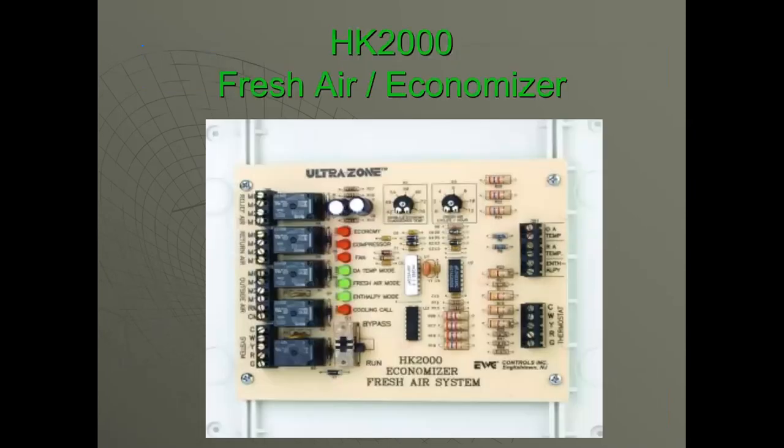As far as our product offering, I'm not going through the panels. I'm just throwing this out here. We do have a fresh air economizer panel. Anybody that's been around the Fort Worth, Dallas area, we are putting these on a lot of systems. Our codes have changed. If they're using anything from 2011 and greater, anything 3 tons and above, or I believe it's 30,000 BTU and above, on a commercial application has to have an economizer on there.